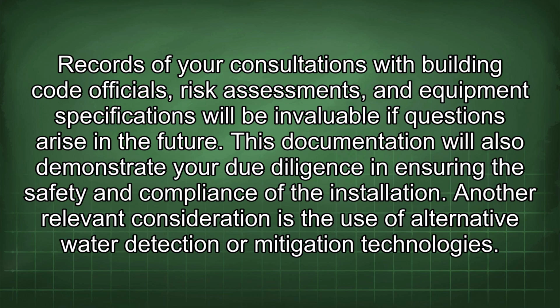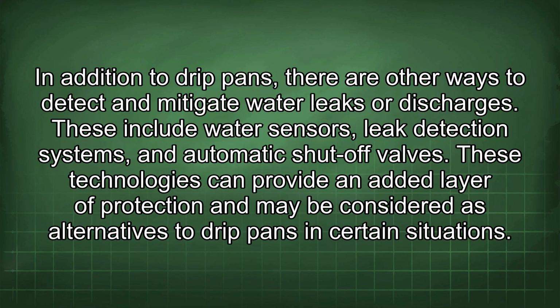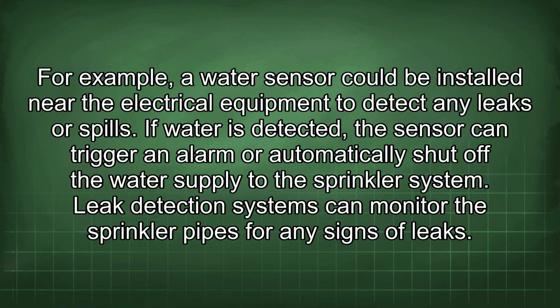Another relevant consideration is the use of alternative water detection or mitigation technologies. In addition to drip pans, there are other ways to detect and mitigate water leaks or discharges. These include water sensors, leak detection systems, and automatic shut-off valves. These technologies can provide an added layer of protection and may be considered as alternatives to drip pans in certain situations. For example, a water sensor could be installed near the electrical equipment to detect any leaks or spills.